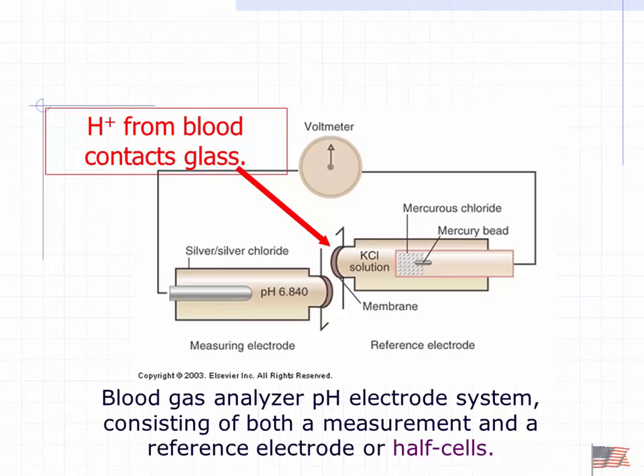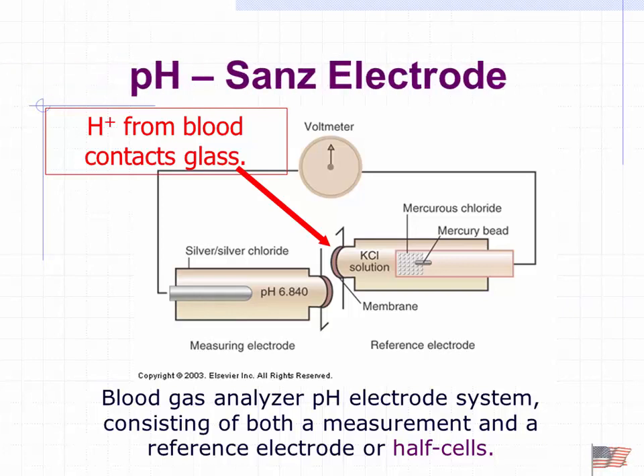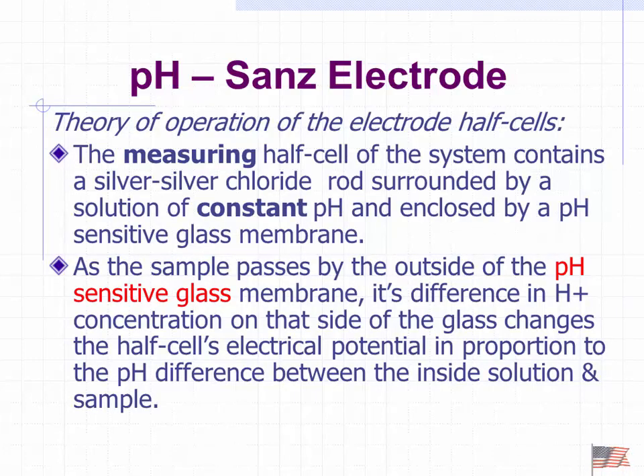So let's talk about the theory of operation. First of all, the Severinghaus electrode, which is basically 2 half cells separated by a membrane, and the blood is then placed so they're adjacent to both of them. Sorry, Sanz electrode. If I said Severinghaus, I meant Sanz. I don't care that you know that it's a silver chloride on one side, and it's something on the other. Just know that there's 2 cells. One's a reference, one's a measurement. And what we're doing is we're comparing the voltage that is there potentially between each other.